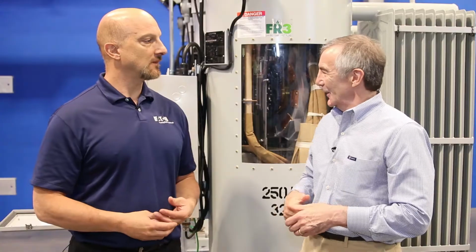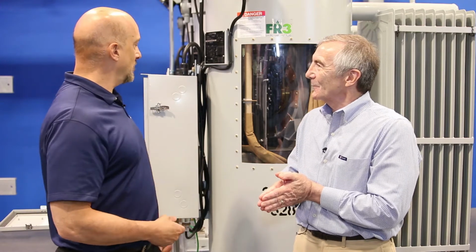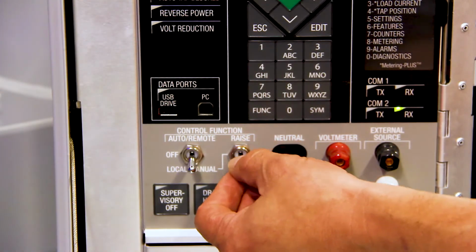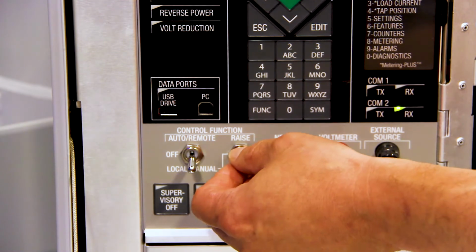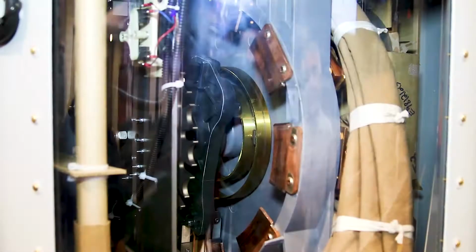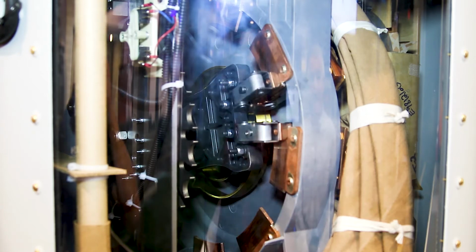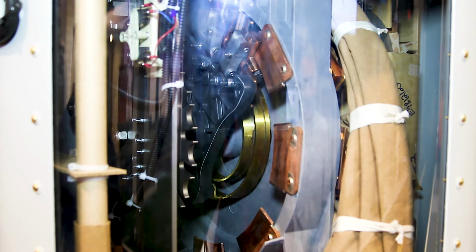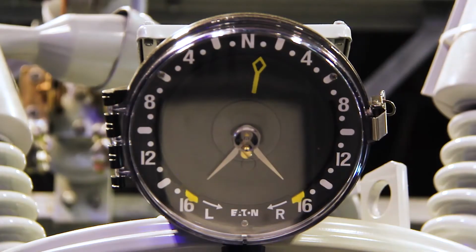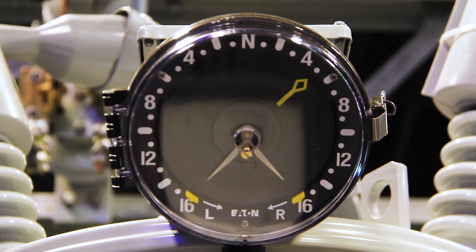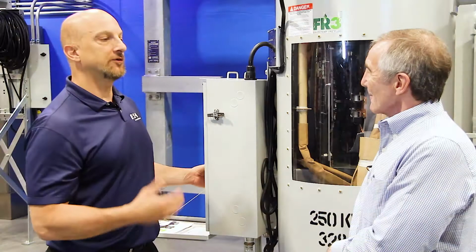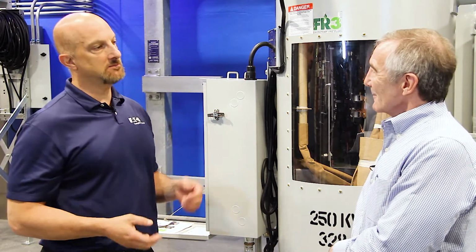I see. Now this regulator, we can actually show what happens when that occurs. Can we do that? Yeah, let me show you how it works. There's a manual control here, and there's obviously a remote control, and you can see this thing is called a tap changer. Inside there, I'm changing the taps, and I can go plus or minus 10%. So for example, if the solar pushes the power into the system and the voltage goes up, the regulator can back off and reduce the voltage to the load, and it does that automatically. And if the solar goes away because there's a cloud, the voltage can go back up. So we can continuously monitor and regulate that.